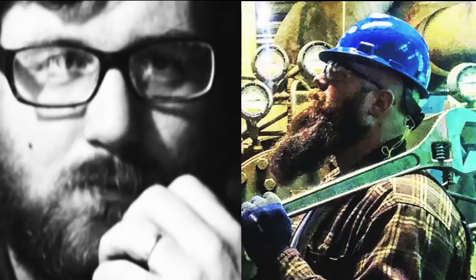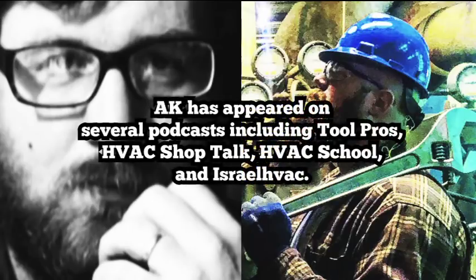When I got to 2 of them, there was clearly water on the floor and the ceiling tile had busted out from soaking through. But once I got my ladder and above the ceiling, everything's bone dry. Not a drip, not a drop, nothing to be seen that indicated a leak. What happens on hot water loops a lot is you'll have joints at either fittings or actuators, valves, things like that, when we're talking about screw pipe, that will leak. But once they are running and get up to temperature, the joints and everything expands and actually seals the leaks up. So if the boiler's been running for a long time, you may not know you have any leaks.